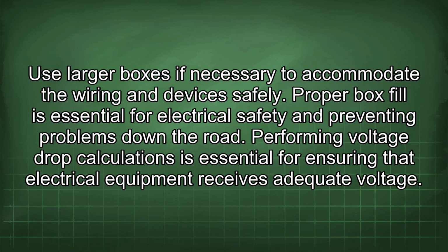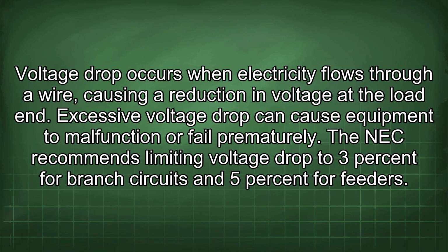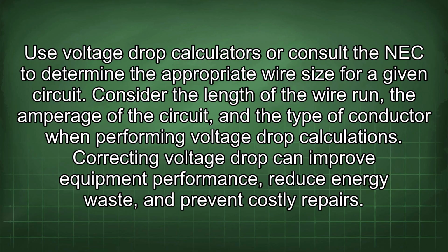Performing voltage drop calculations is essential for ensuring that electrical equipment receives adequate voltage. Voltage drop occurs when electricity flows through a wire, causing a reduction in voltage at the load end. Excessive voltage drop can cause equipment to malfunction or fail prematurely. The NEC recommends limiting voltage drop to 3% for branch circuits and 5% for feeders. Use voltage drop calculators or consult the NEC to determine the appropriate wire size for a given circuit. Consider the length of the wire run, the amperage of the circuit, and the type of conductor when performing voltage drop calculations. Correcting voltage drop can improve equipment performance, reduce energy waste, and prevent costly repairs.